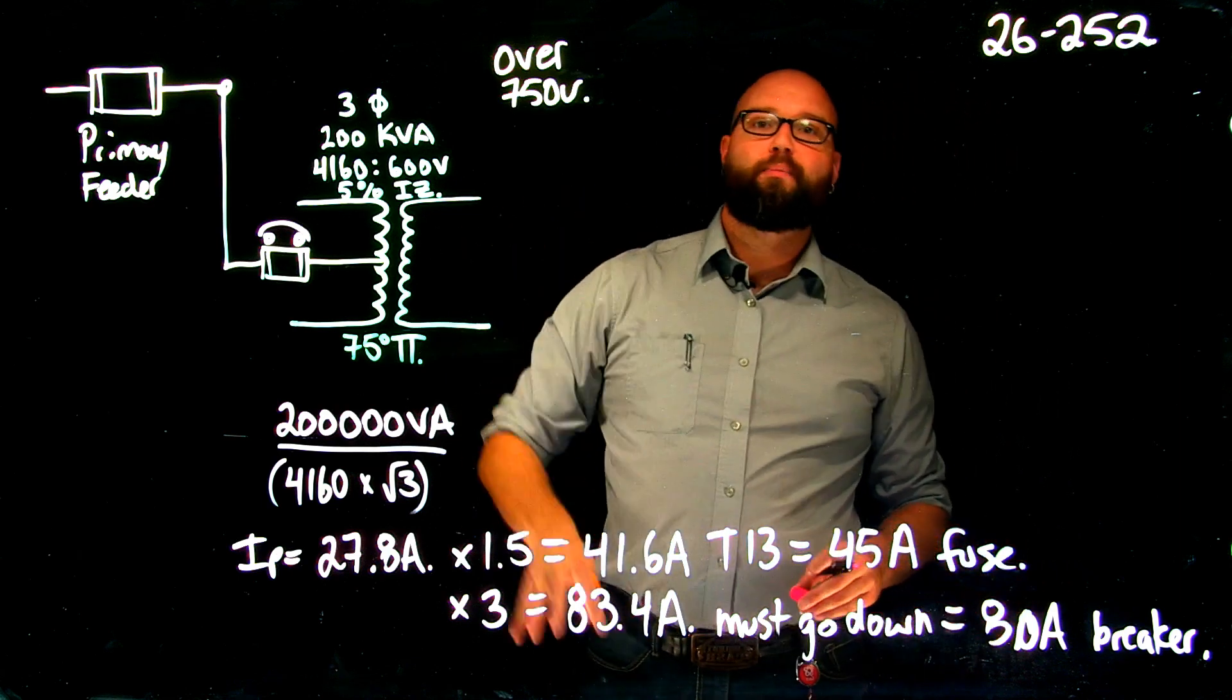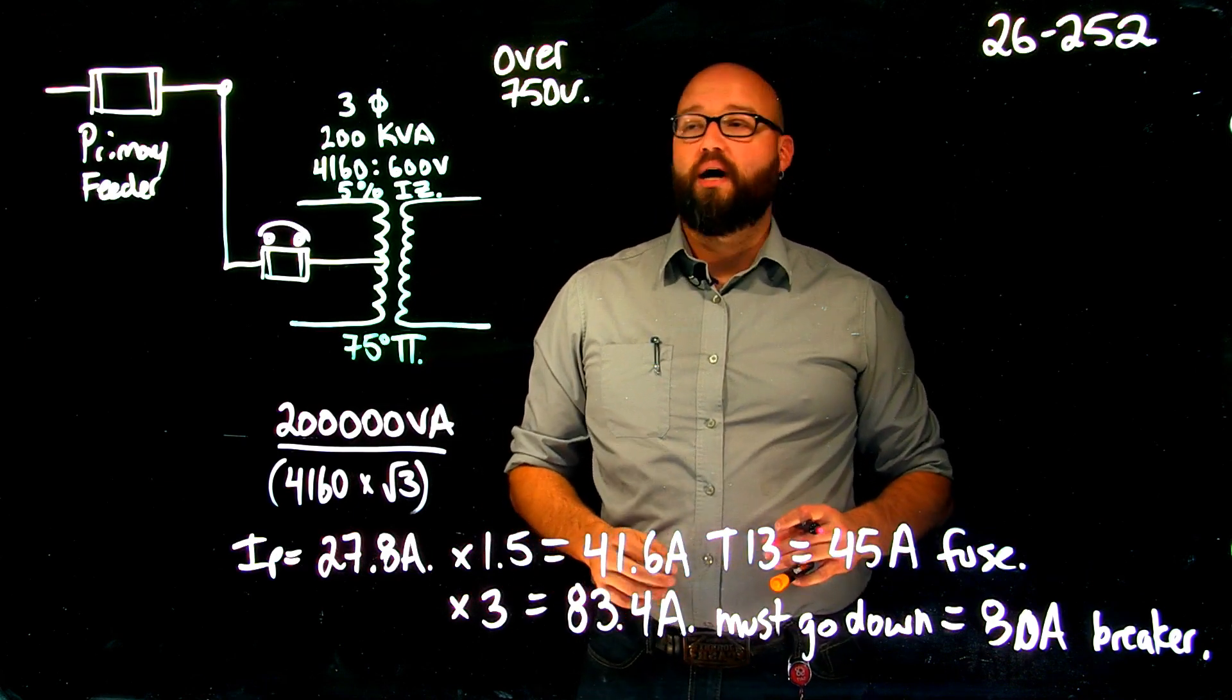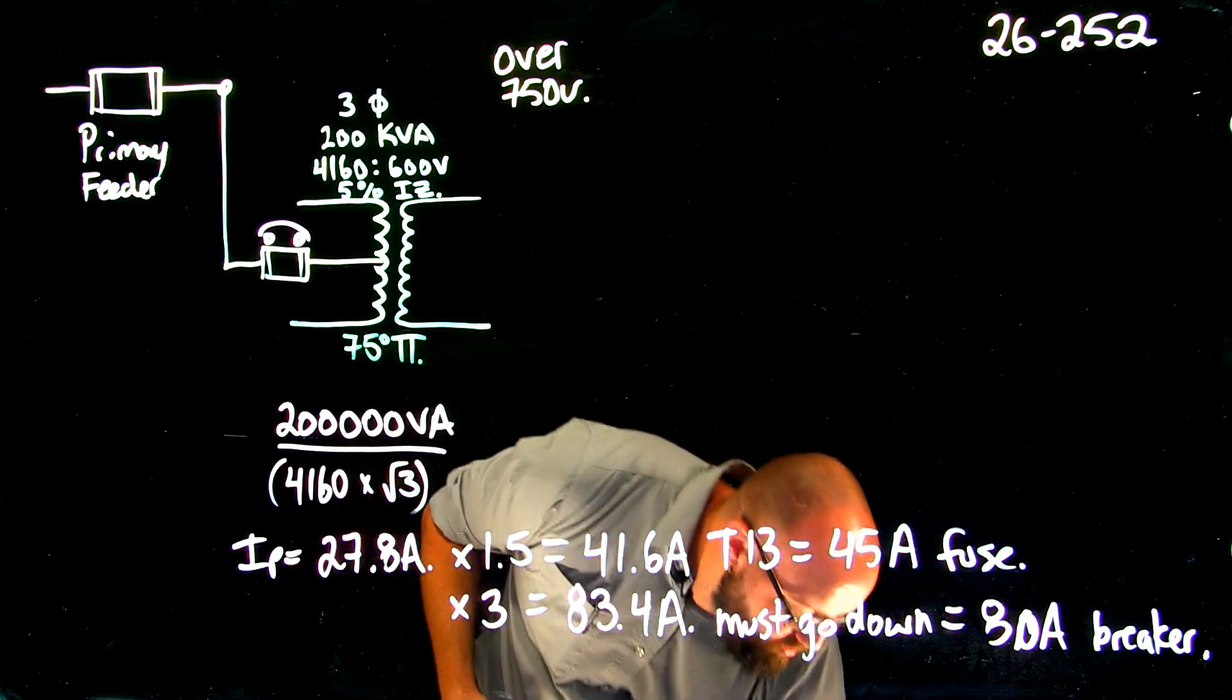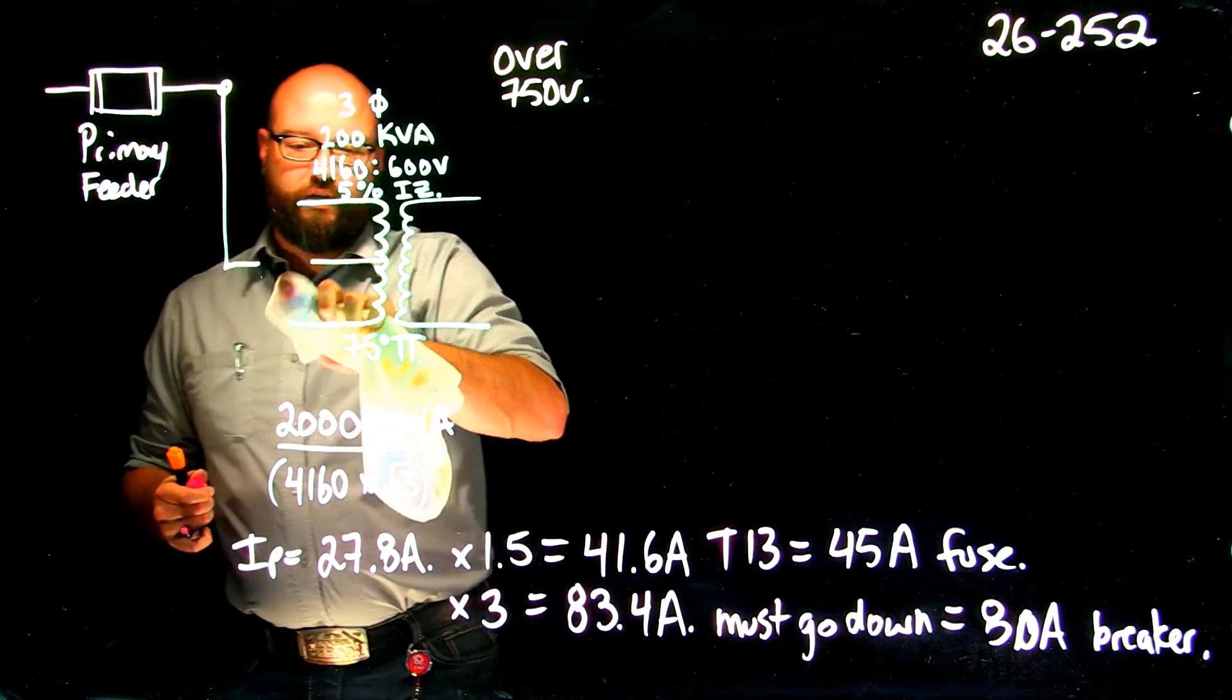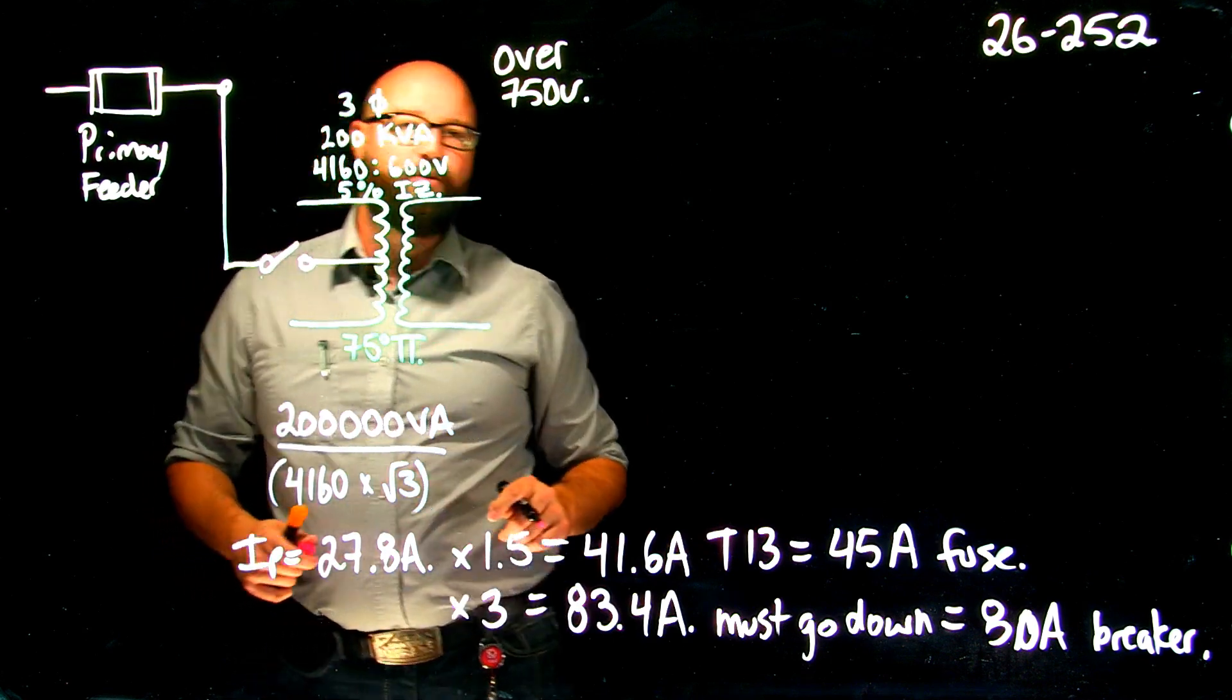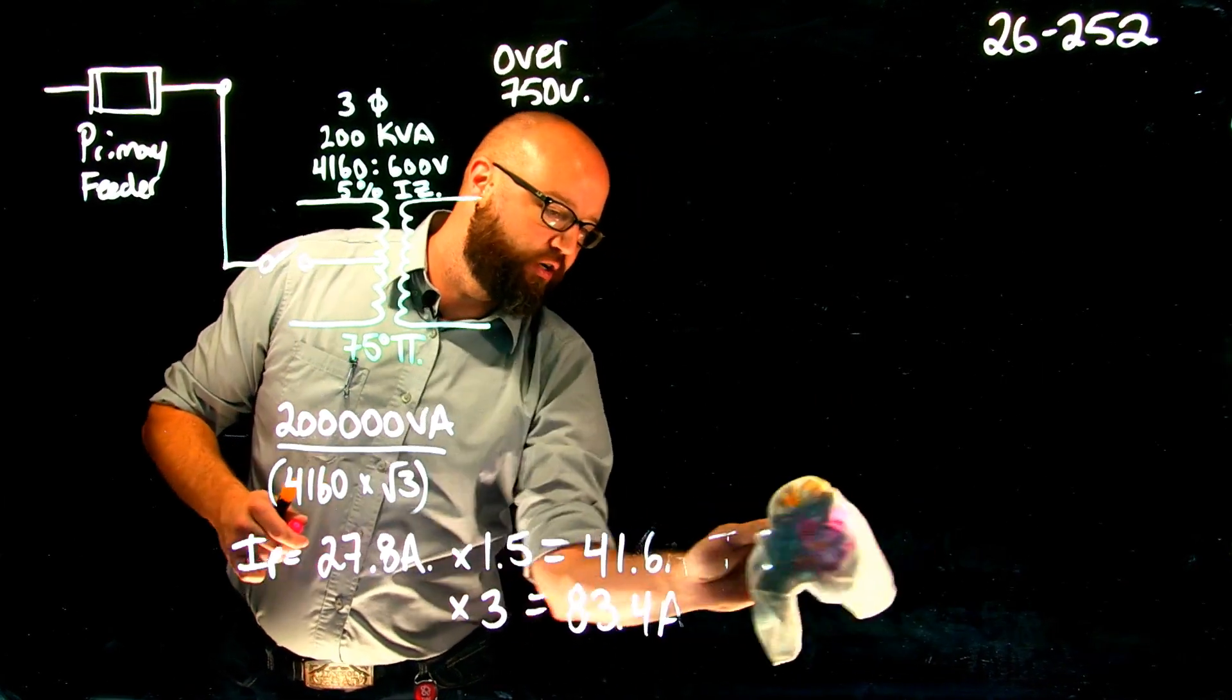This is only primary protection. There is no secondary protection. It tells me that if I have a load fed off the secondary, my primary protection will adequately protect the secondary of my transformer. We don't need to worry about the primary feeder because that would be sized independently in this case. What we're going to worry about next though, is what happens if we want to omit this primary protection. We're allowed to do that, but under very special conditions. If I wanted to get rid of this primary protection, I still have to have some type of disconnecting means. Maybe we have an unfused disconnect in there that still disconnects my transformer.